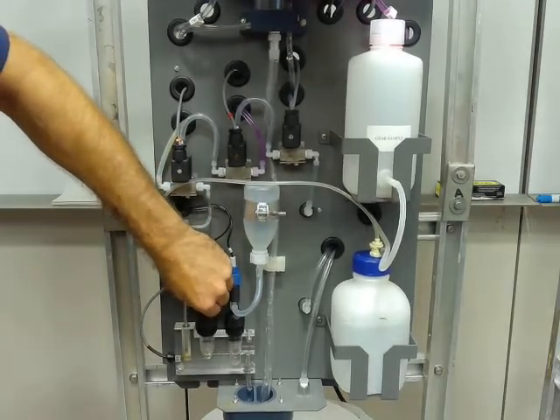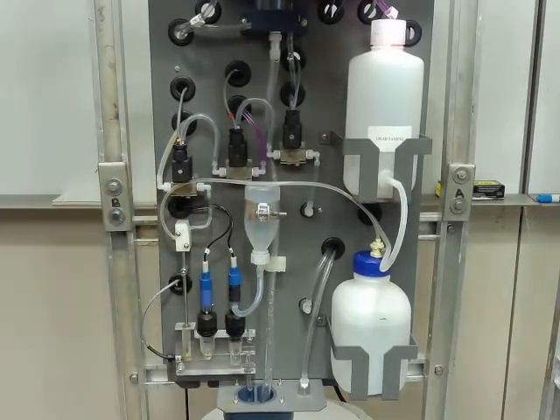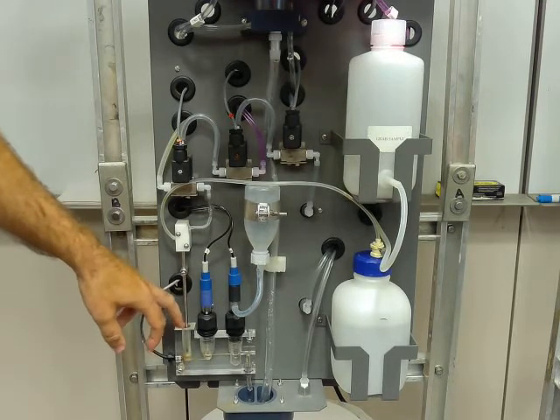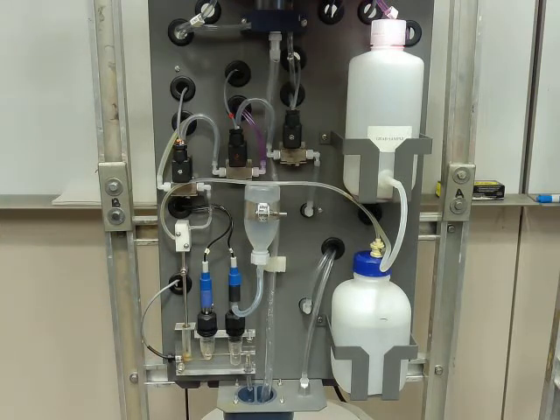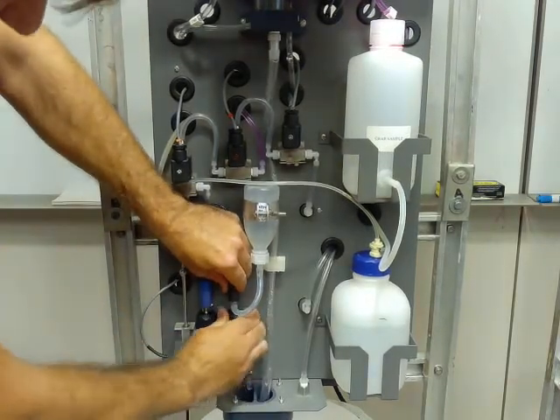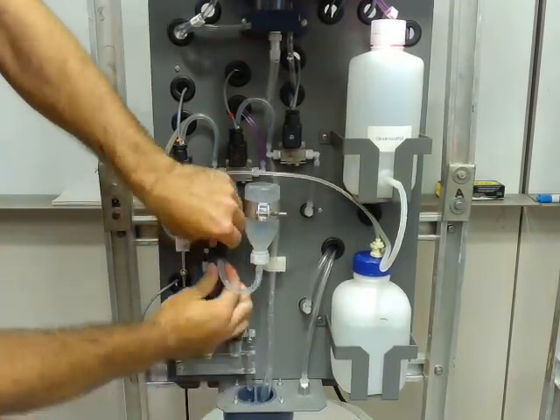When it comes to placing those probes, the measuring probe goes just off the bottom of the flow cell. You don't want to block the flow path of the sample through the flow cell. You would start to get a little bit of overflow coming out this top side. And obviously, if it's not flowing properly, you're not going to get a good reading. With the reference electrode side, the electrode goes in the same way.